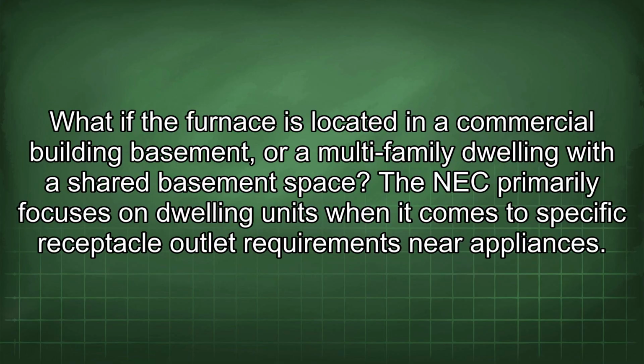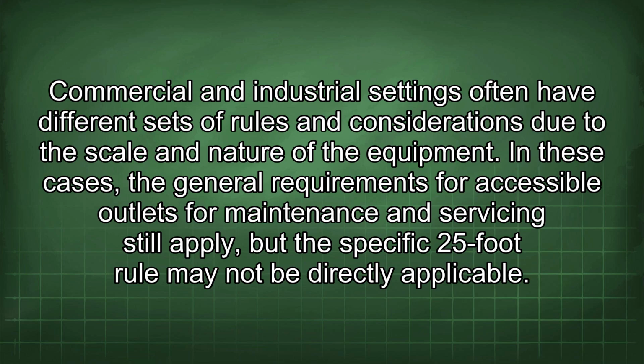What if the furnace is located in a commercial building basement or a multi-family dwelling with a shared basement space? The NEC primarily focuses on dwelling units when it comes to specific receptacle outlet requirements near appliances. Commercial and industrial settings often have different sets of rules and considerations due to the scale and nature of the equipment. In these cases, the general requirements for accessible outlets for maintenance and servicing still apply, but the specific 25-foot rule may not be directly applicable.